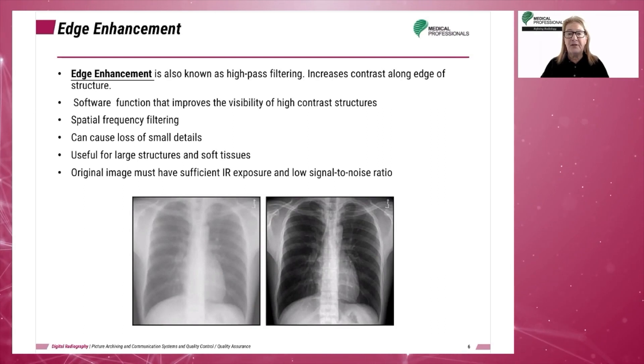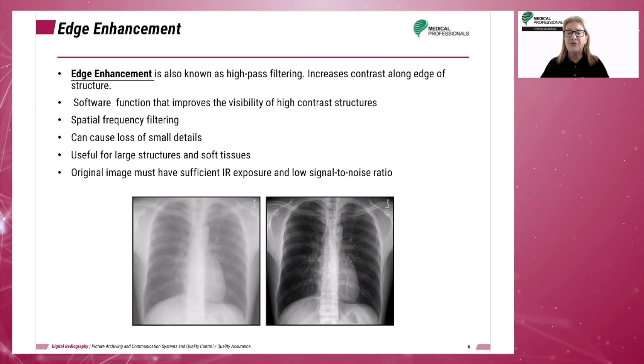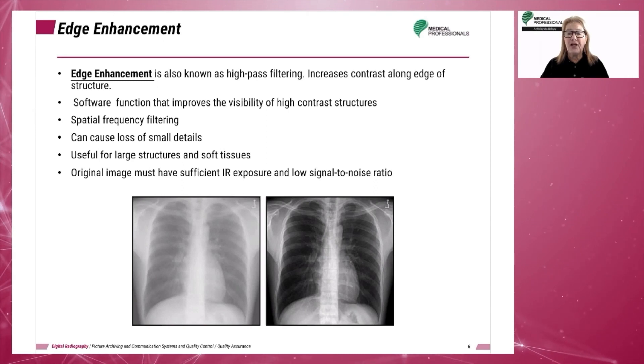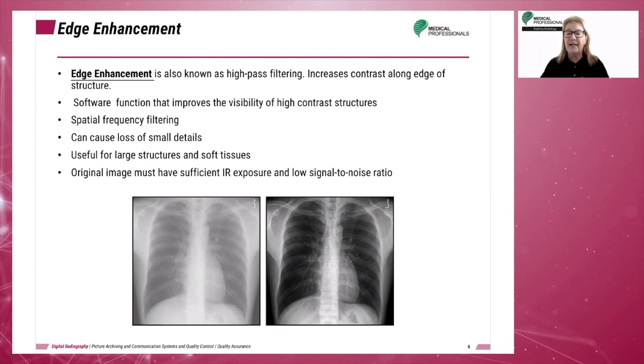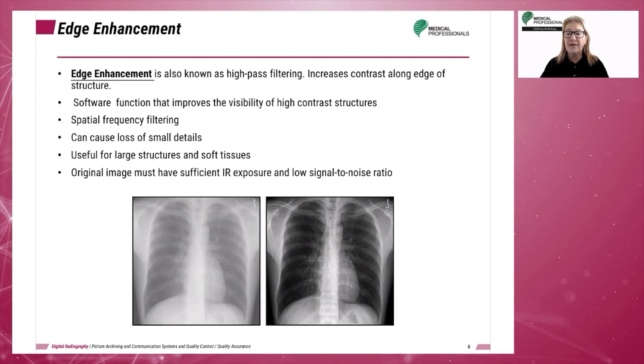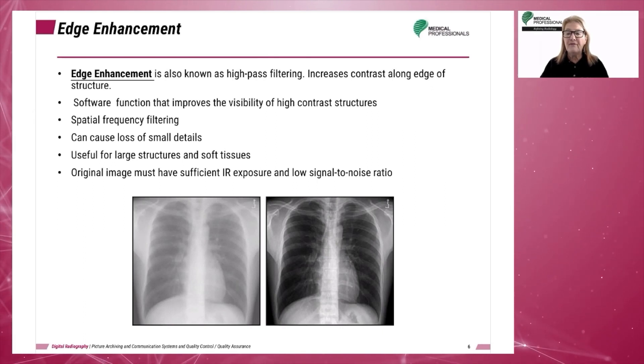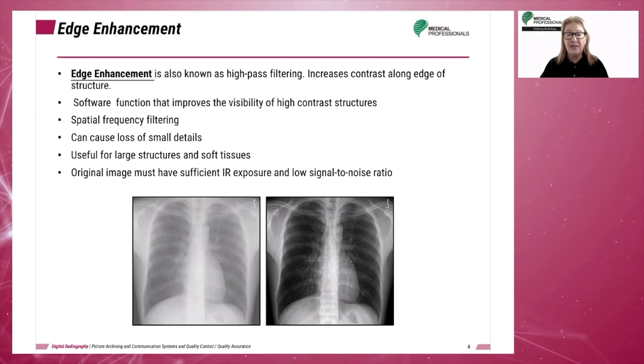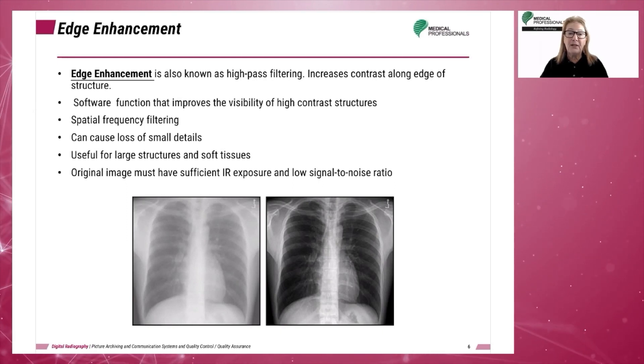Edge enhancement is another software function that uses an algorithm to convert the image into the spatial frequency domain. The algorithm averages the signal strength of adjacent pixels in the image data. Carter and Veal refer to this as a neighborhood and state that edge enhancement occurs when there are fewer pixels in the neighborhood included in the signal average. When the frequencies of the region of interest are known, those frequencies can be amplified and other frequencies can be suppressed, producing an image with increased contrast.